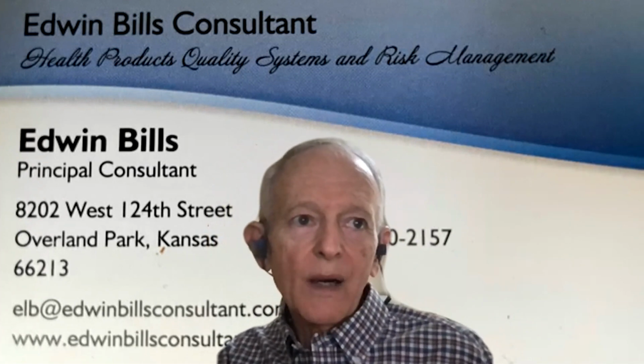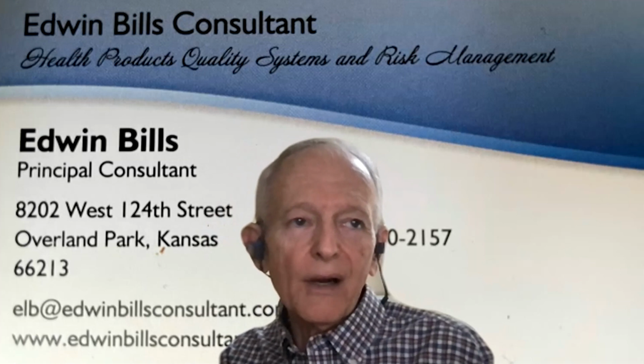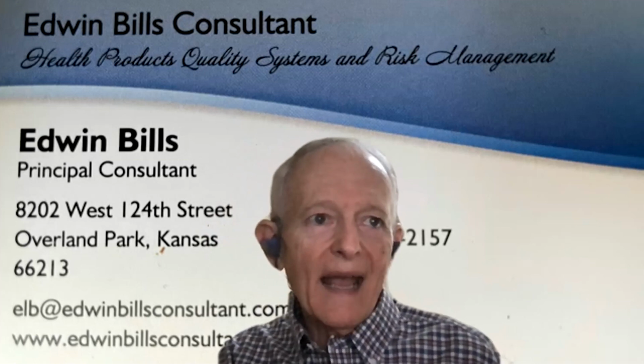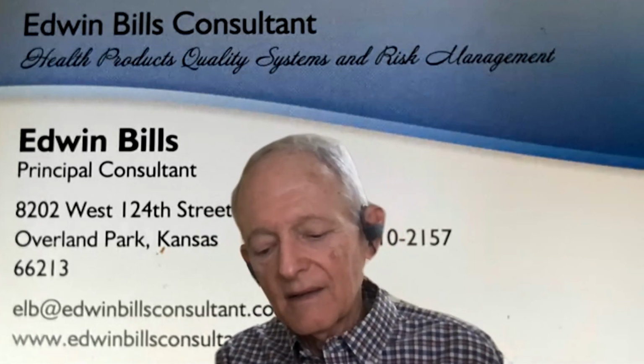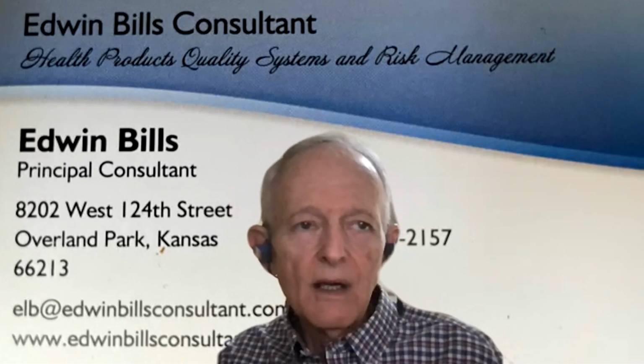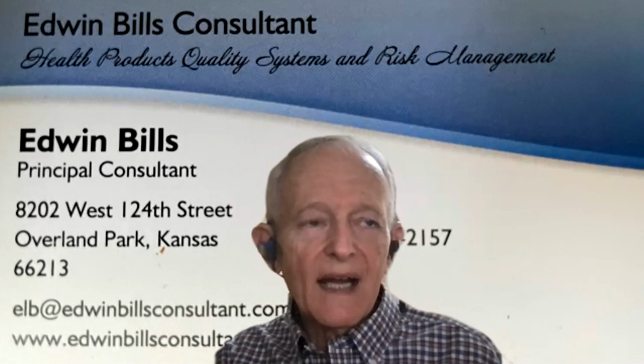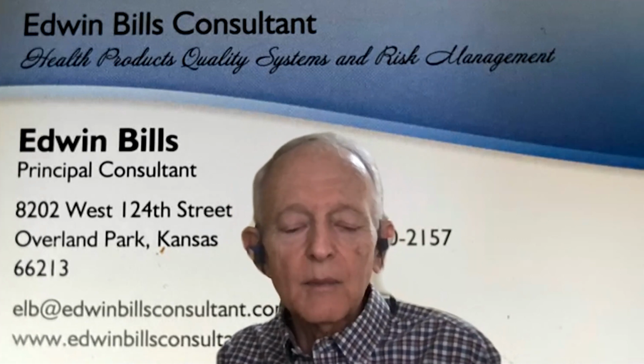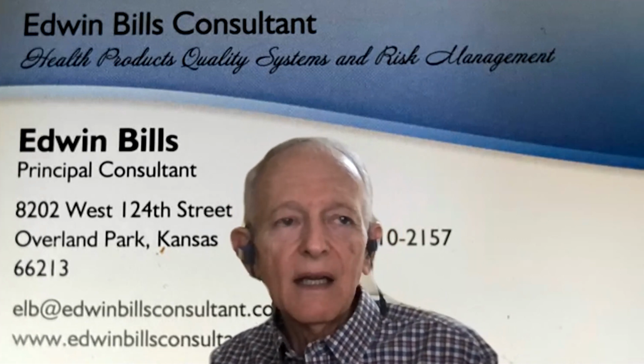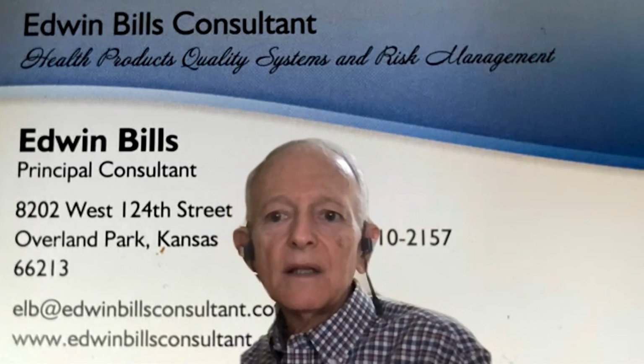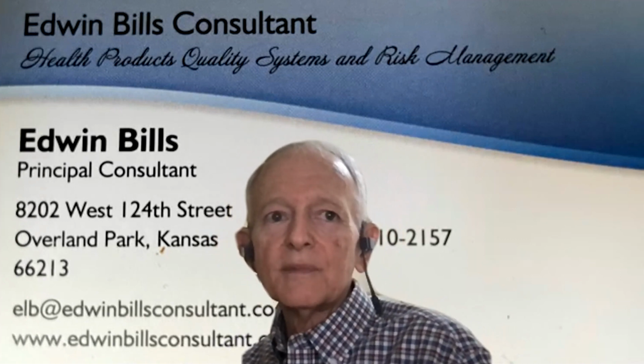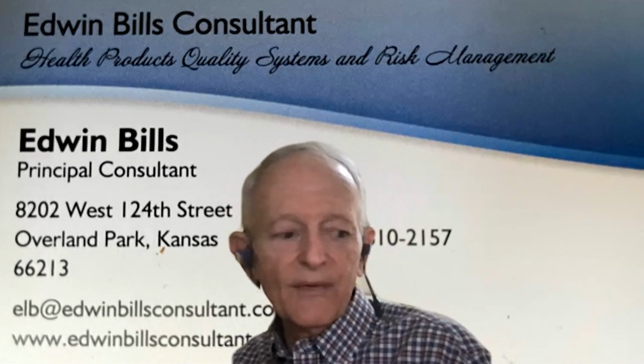In fact, it requires you to do risk analysis before the clinical trials to identify hazards that the patient, in this case, might be exposed to during the clinical trial. And you have to inform them of the risks that are associated with it. So your benefit side a lot of times comes from that clinical trial activity. Yes. So there's where some of your data is going to come from to conduct this benefit risk.